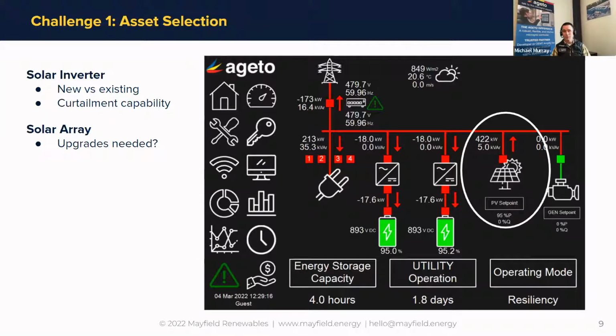One thing you might also need to check out is if you do replace a solar inverter, see if the string voltages are still going to match with the new inverter, and also check if it'll trigger any requirements for rapid shutdown or coming up to code on the solar installation. It's probably still the best thing to do, but be aware of those potential costs when you're integrating with solar.